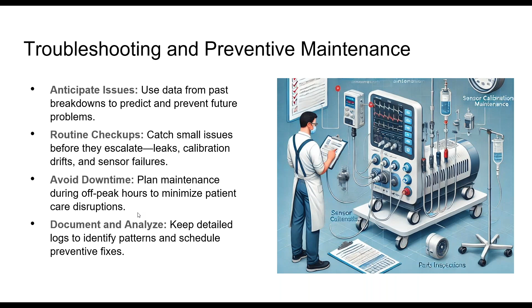Document, and analyze that data. Don't just document for the sake of documenting. If you're writing down electrical safety values, for example, I would suggest you don't. That's a whole other topic that anybody who's willing to talk to me about it, we can talk about. But there's no need for that in general, but there is, I believe, for other aspects like the volumes, the pressures, and the flow rates that you got on a particular ventilator, because it could come up in litigation about how detailed you were. It could come up as an important aspect about why maybe the ventilator worked and the user had a problem with it still. Does that make sense? Like a use error.